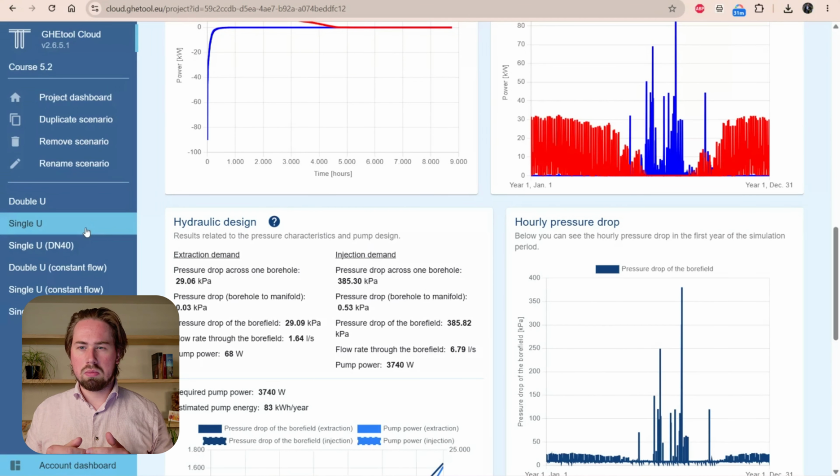So that's what I wanted to give you, or insights I wanted to share with you when we're talking about single versus double U probe from the hydraulic perspective. And as you can see, again, here there is no definitive conclusion. It really depends on your situation. There is a definitive conclusion between working with constant and variable flow rate. Please work with variable for pump energy consumption. But on which one is definitely better, it really depends on your situation, and it's important to simulate different situations as well. Now, this was what I wanted to say in these two chapters about single versus double.